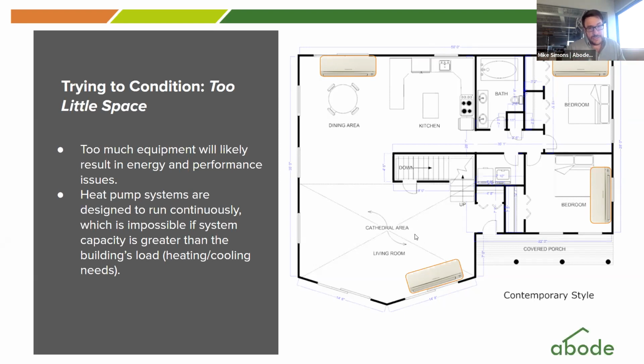One of the things we deal with as heat pump consultants is if you put four units on one outdoor unit, the smallest outdoor unit that supports it is 36,000 BTUs. The load is 18, this is providing 36. It's 2x oversized, and that becomes slightly what we would call risky as far as performance goes.